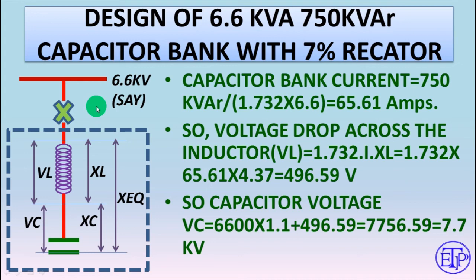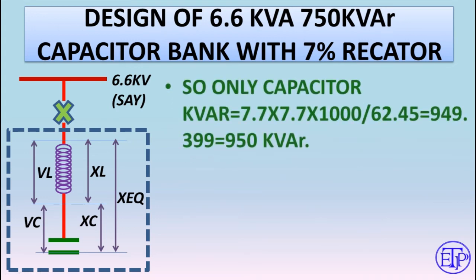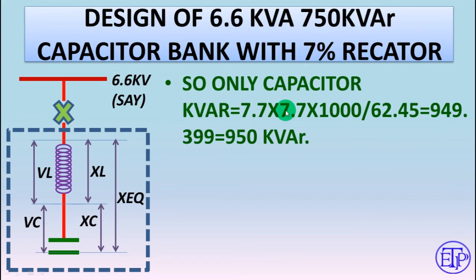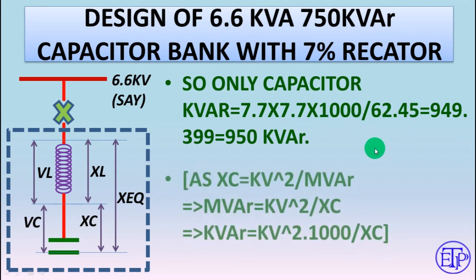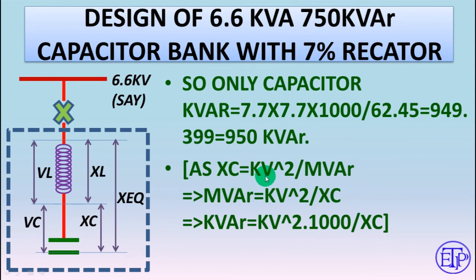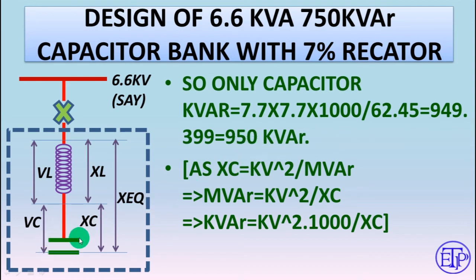Now we need to find the KVAR of the capacitor alone. It is calculated as kV² × 1000 / XC. Using VC = 7.7 kV and XC = 62.45 ohms, this gives 950 KVAR. So for a 750 KVAR bank, you must select a capacitor rated at 950 KVAR — not 750.